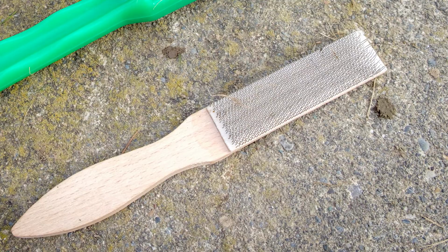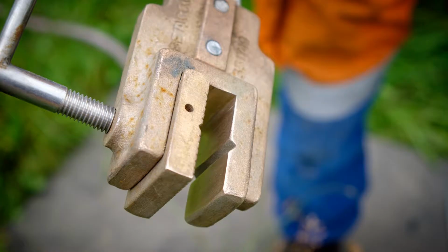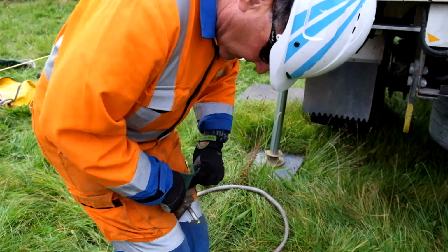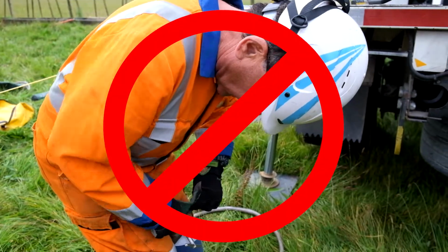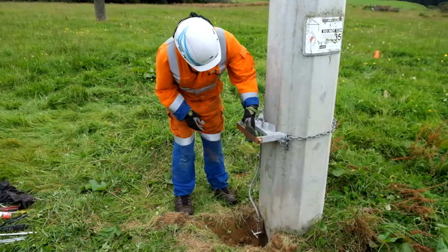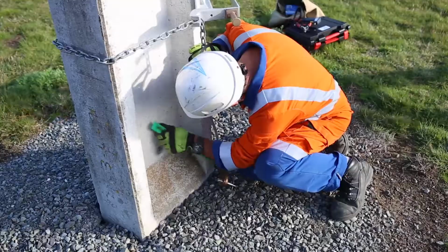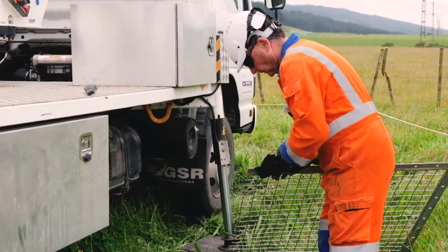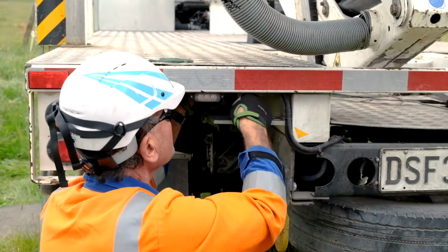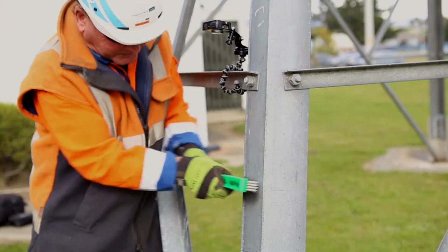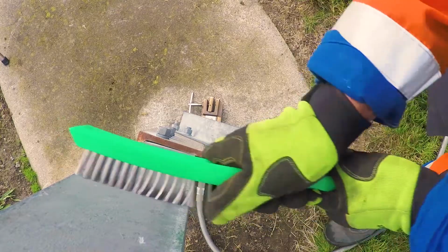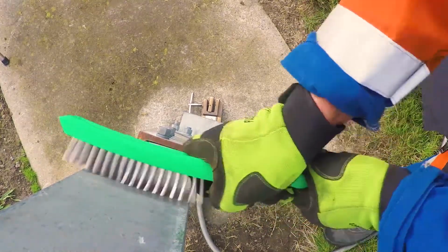Cleaning a tail clamp is really easy. You can use a metal brush with short bristles. Give the fixed smooth surface of the tail clamp a good clean. You will be able to see the shiny copper surface easily after the clean. Don't use a Scotch-Brite pad or emery paper with your finger, as this will round off and just polish the edges. A clean tail clamp alone is no guarantee of a good connection. The contact surfaces they are to be attached to must also be clean. Again, it is essential that all contact surfaces are clean for correct earthing.